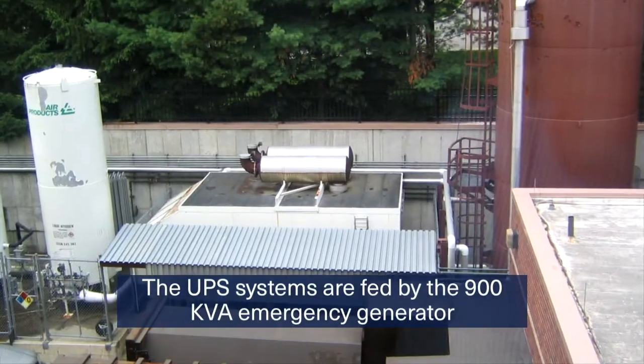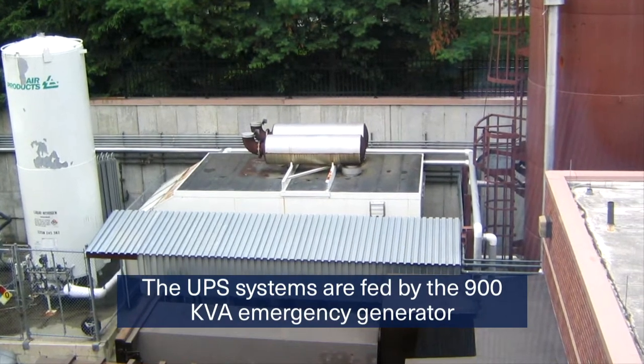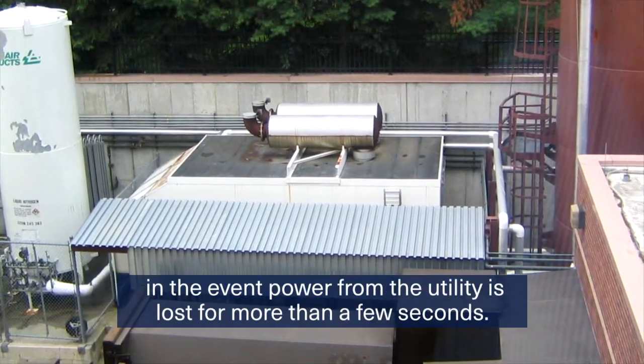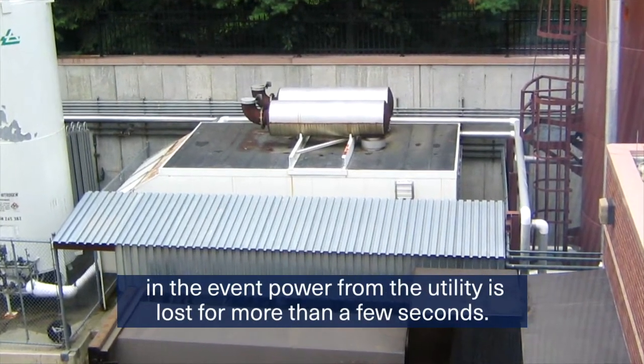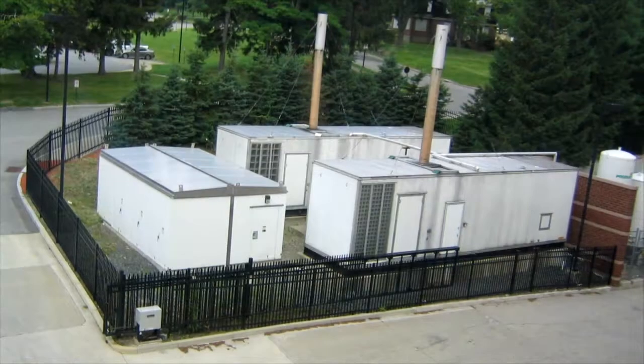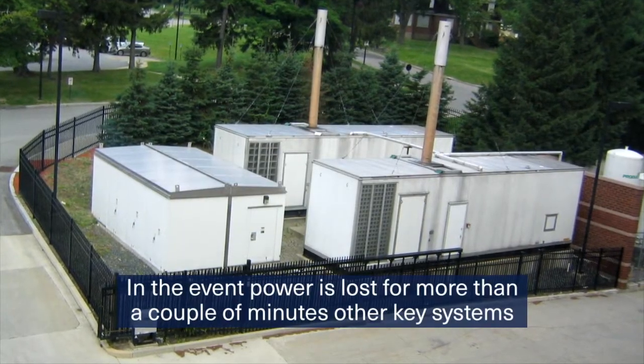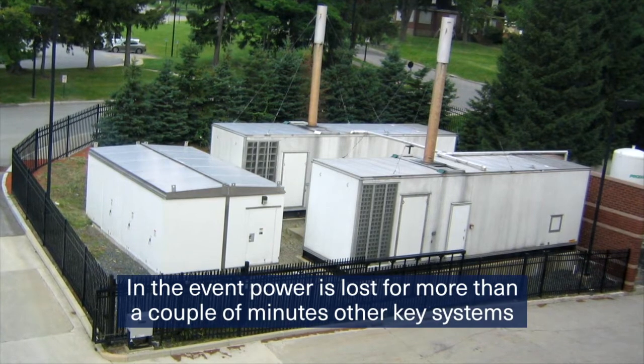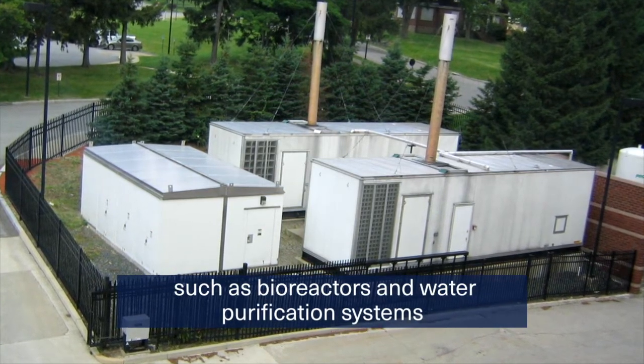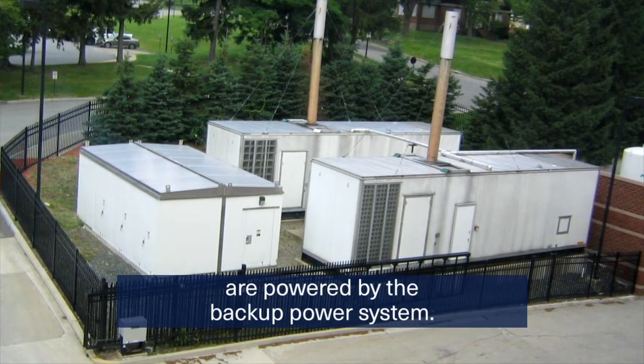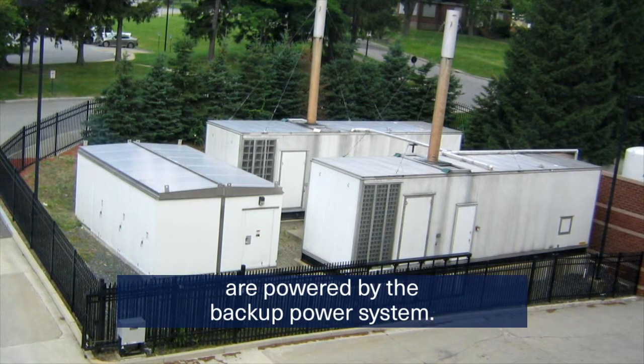The UPS systems are fed by the 900 kVA emergency generator in the event power from the utility is lost for more than a few seconds. If power is lost for more than a couple of minutes, other key systems, such as bioreactors and water purification systems, are powered by the backup power system.